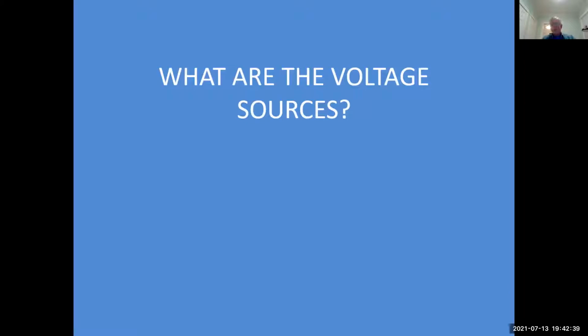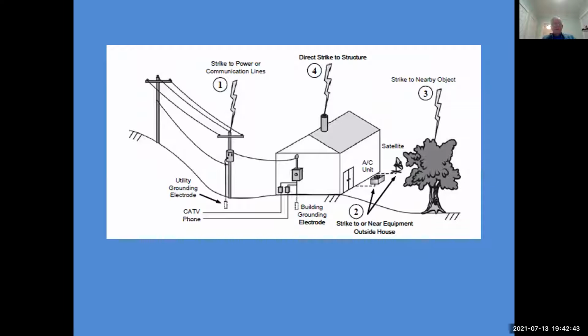And where these voltage inputs come from, it can be lightning strokes to power lines and comm lines. It can be strikes to the structure. There can be electrical faults. You can have a primary distribution wire fall on the secondary distribution, where all of a sudden you're going to see this spike, and there will be a spike even on the secondary side of the transformer that can be significant when it gets to your house.